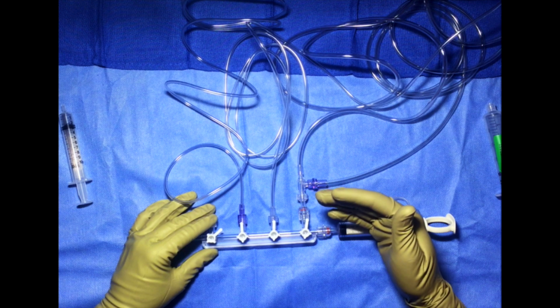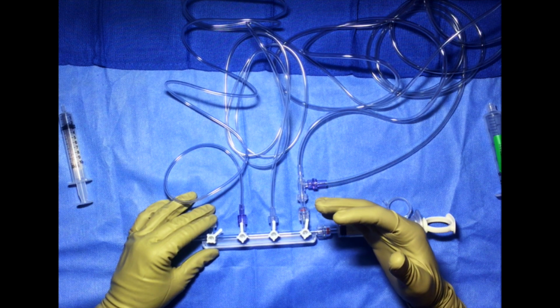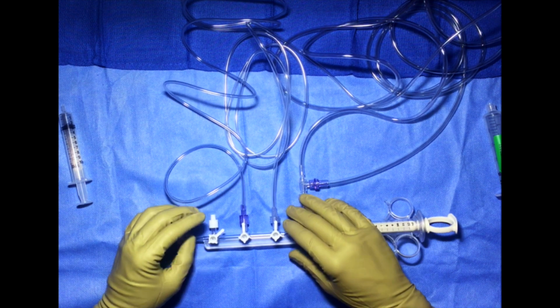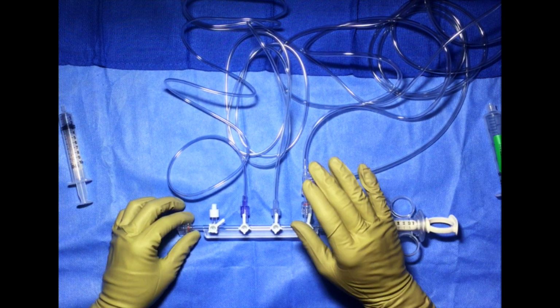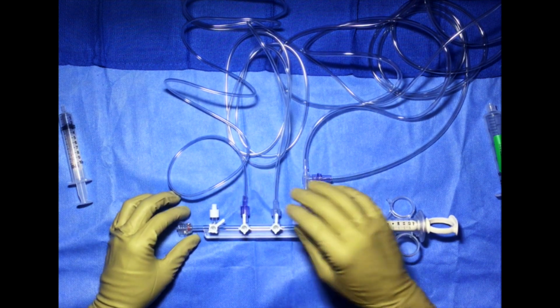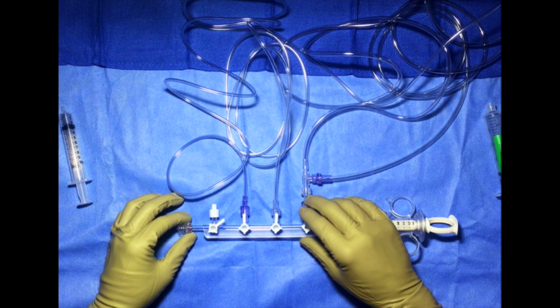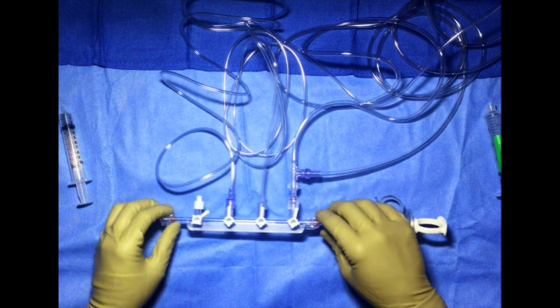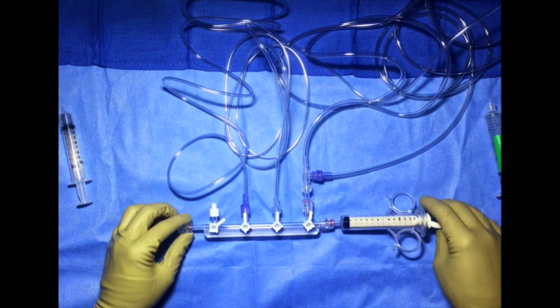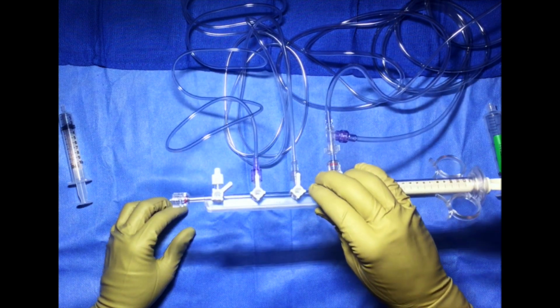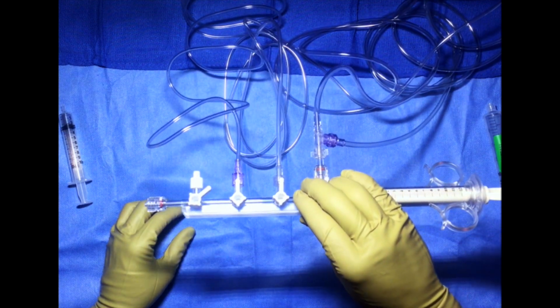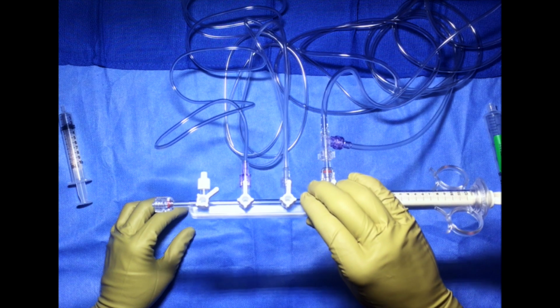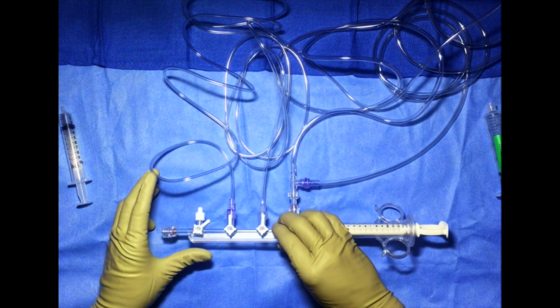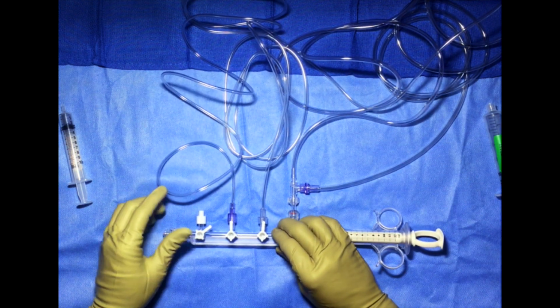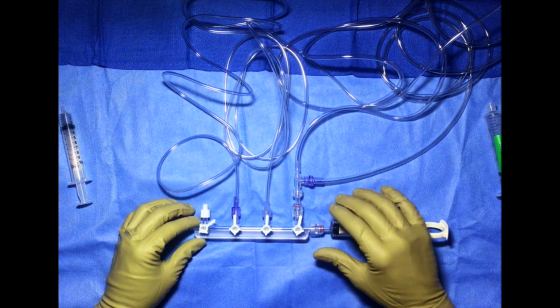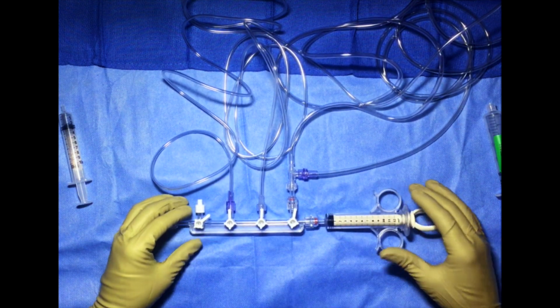As long as the bed, on the actual bed should be okay because the patient's moving too, which is what you would want. If you have this regular transducer zeroed at this point, and then you move things up here, and then the doctor's holding it up here, if we're up off the table higher, our pressures are falsely low. If they're too low, they're falsely high because of the atmospheric pressure and all that sciencey stuff.